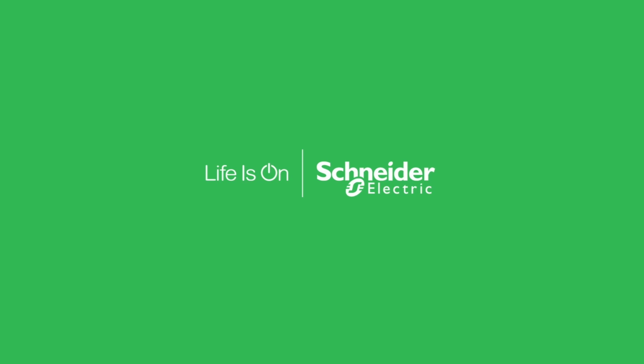Here's another really good one, Eric, timely as well. We had a problem of oscillation of power in a multi-unit split phase arrangement. Is there something to consider to avoid oscillation of power for each unit? Oh, that's a good one. First and foremost, always have the latest and greatest firmware. And secondly, if you're still having issues, you can calibrate your output voltages to be closer to each other. They should be within a volt or two from the factory, but they may need to be calibrated a little bit closer. But I would say that with the latest firmware, you should not have to deal with any of that. Let me jump to another question, Eric.